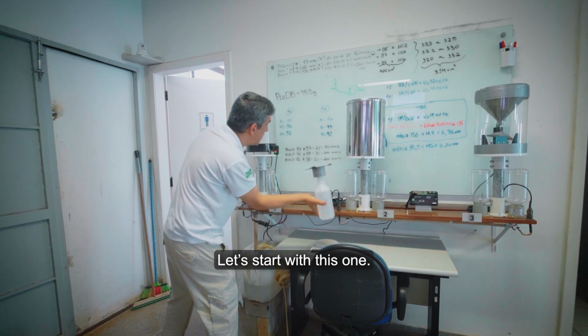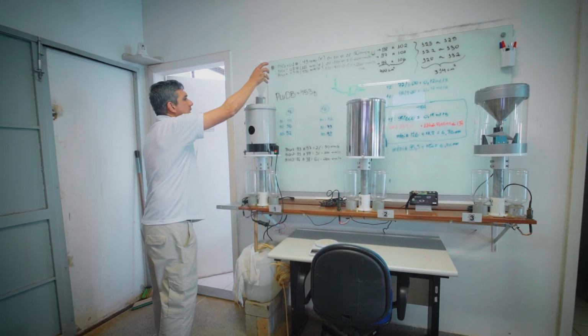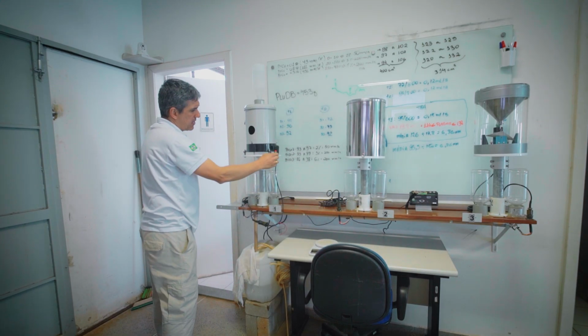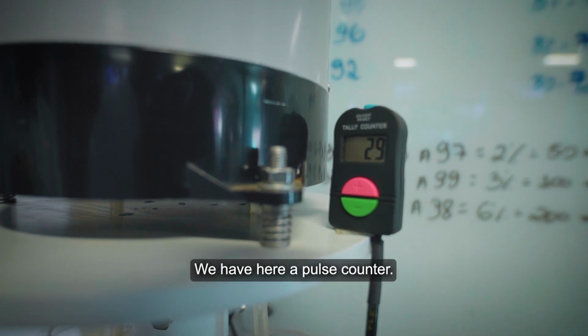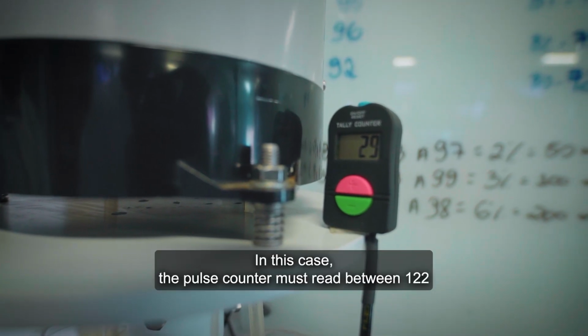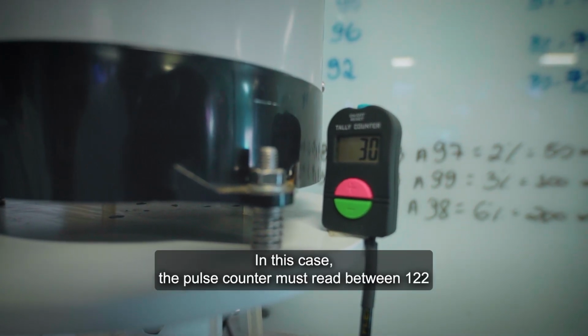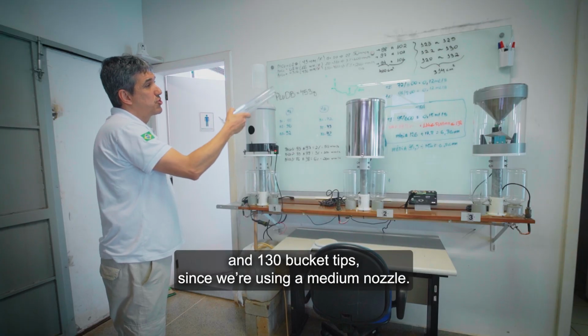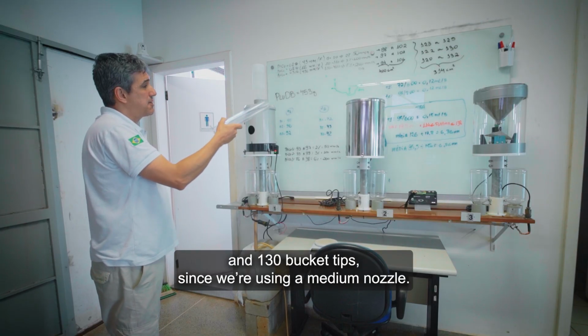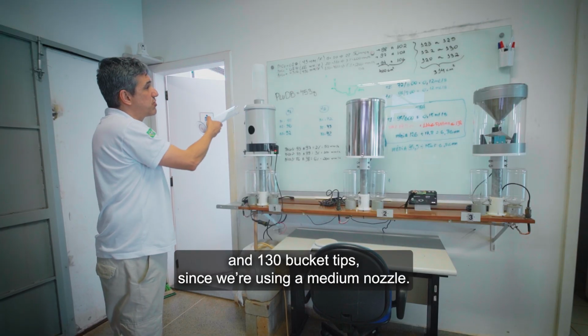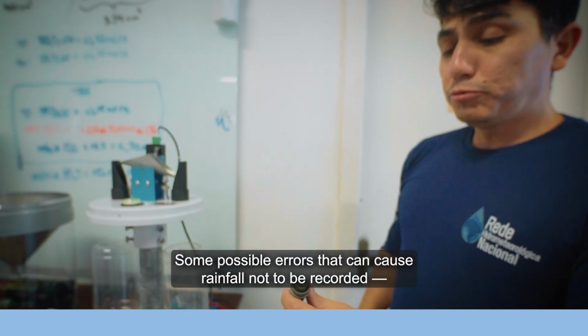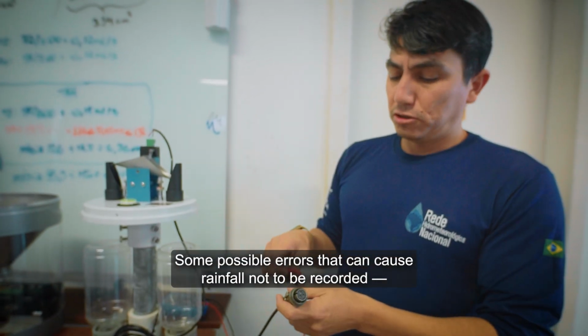Let's start with this one. We have here a pulse counter. In this case, the pulse counter must read between 122 and 130 bucket tips, since we're using a medium nozzle. Some possible errors can cause rainfall not to be recorded.